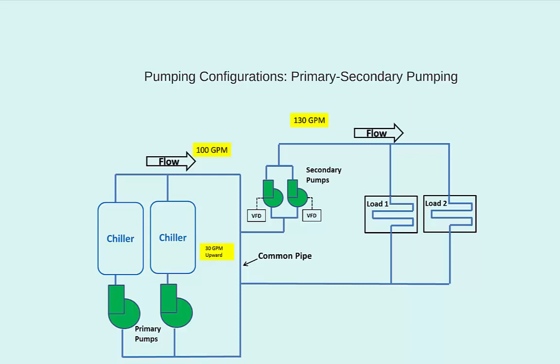It is very common these days, but does have some inherent downfalls which we will discuss later on in the course. A big takeaway here is that the primary pumps are to be constant speed, while the secondary pumps are to be variable speed. Constant speed primary pumps maintain a constant flow through the primary equipment. The reasons why we do this will be discussed later on in the course. Variable speed secondary pumps allow us to change the flow rate going to the coils depending on the cooling requirements in this example. Reducing flow at lower loads helps save on pumping energy that is being consumed.